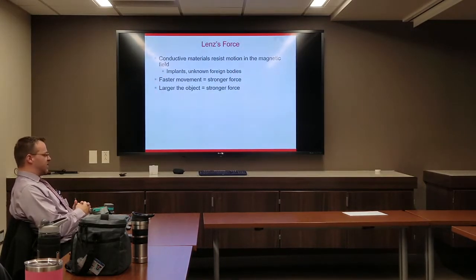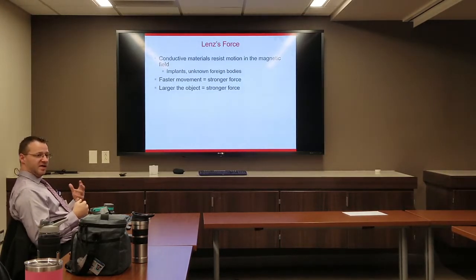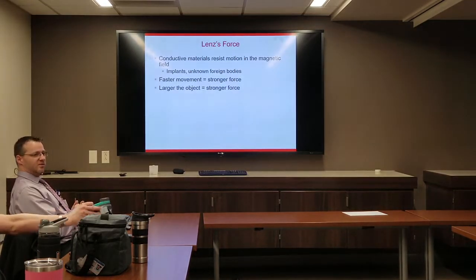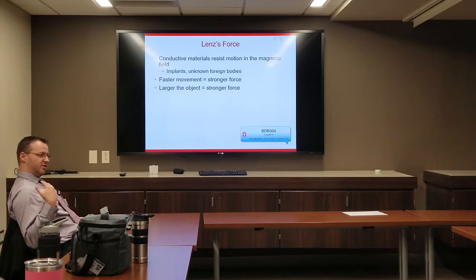Lenz's forces (eddy current forces) are ones that people aren't generally as familiar with. Conductive materials will resist motion through a magnetic field. Primarily, anything metallic that isn't ferromagnetic is going to experience these Lenz's forces. The faster you move through the field and the larger the object, the stronger the force. For instance, if a patient has a conditional pain pump, moving them through the field quickly may cause them to feel a tugging or pulling on the device. Moving patients slowly reduces the force on any object.